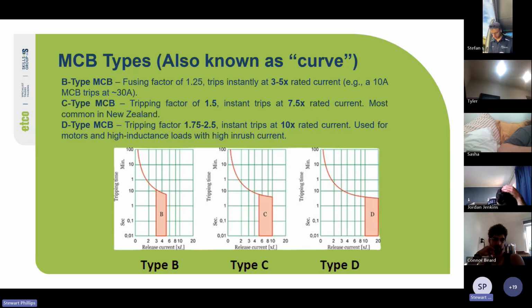So there are different types of MCB, also known as curves. Sometimes they'll be called B-type, C-type, and D-type, other times B curve, C curve, and D curve. So if you look at a breaker and it says C10, it's a C curve 10 amp breaker. A B-type has a fusing factor of 1.25. It trips instantly at 3 to 5 times its rated current, so a 10 amp MCB trips at 30 amps. C-type MCB has a tripping factor of 1.5 and trips instantly at 5 to 10 times its rated current. It's the most common in New Zealand because we use it all through domestic. D-type has a tripping factor of 1.75 to 2.5 and trips instantly at 10 times rated current, so it's used for motors and high inductance loads with high inrush current.